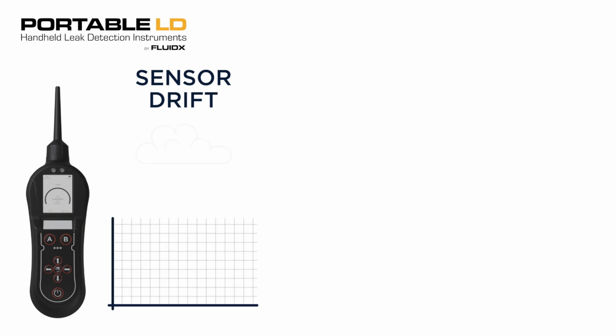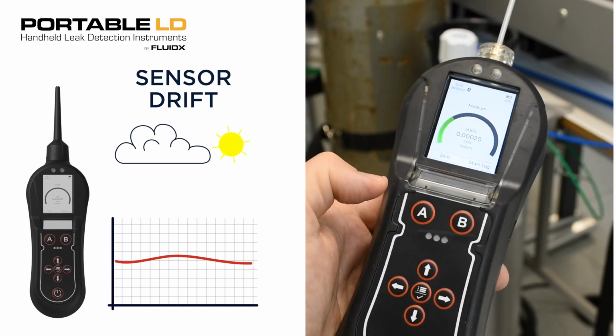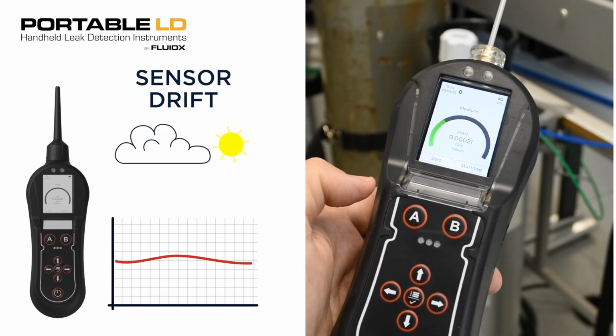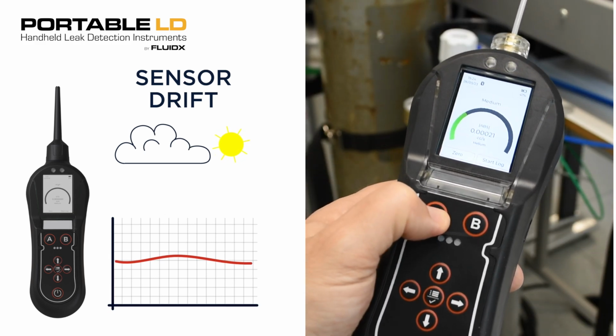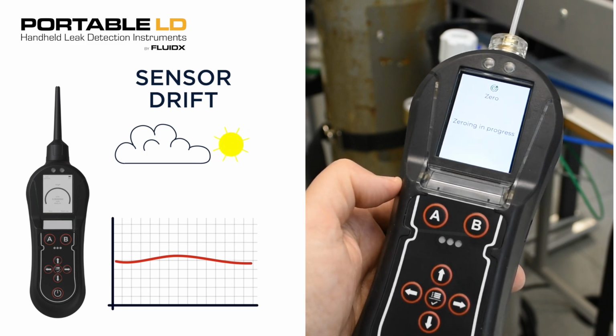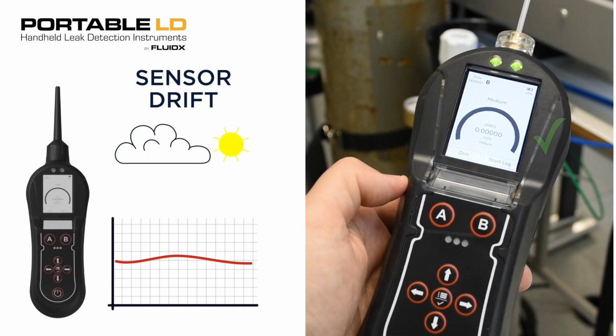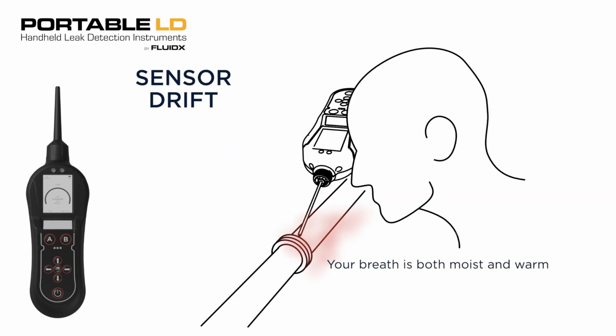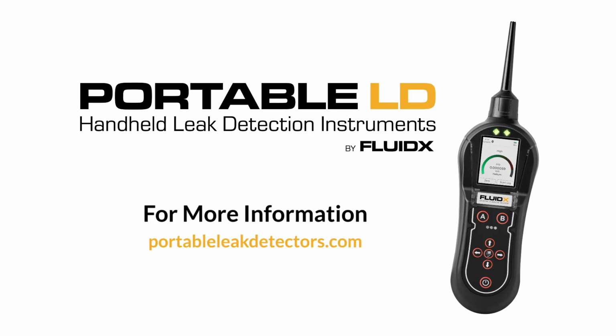Over time, thermoconductivity sensors may drift slightly due to changes in humidity or temperature. If this happens, simply remove the Panther from the test area and press the 0 button. After a few moments, the device will be ready to continue testing. One final note: since breath is both warm and moist, avoid exhaling over the test area, as this can affect readings.